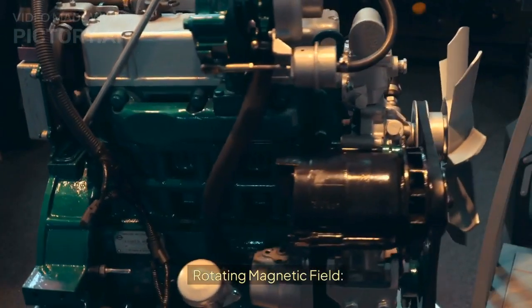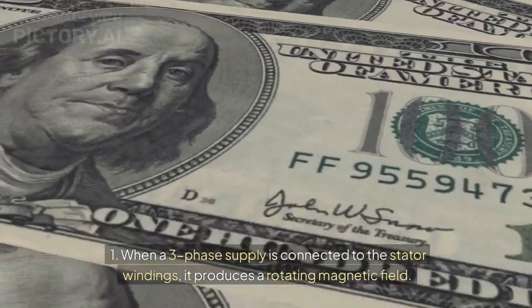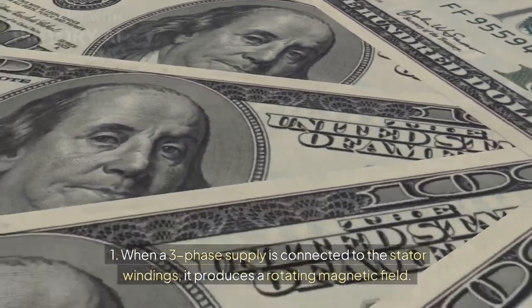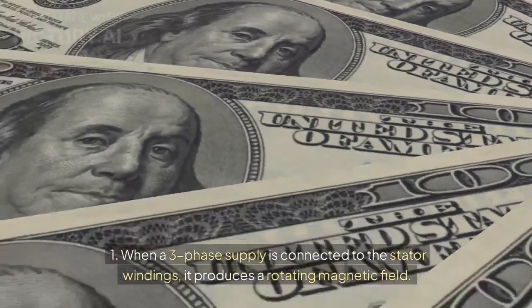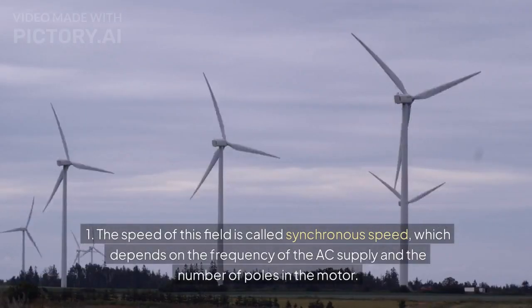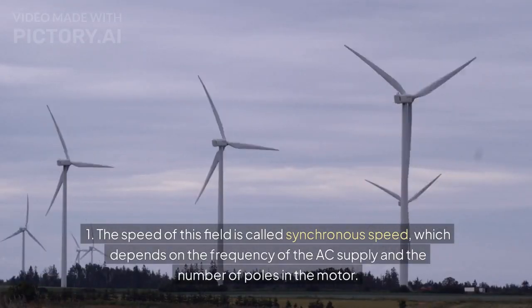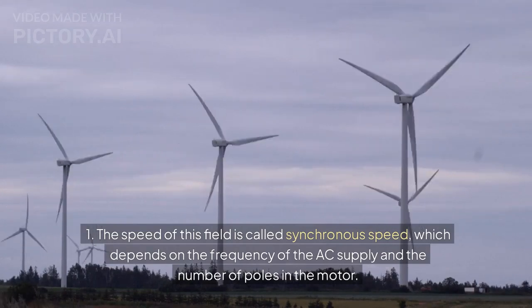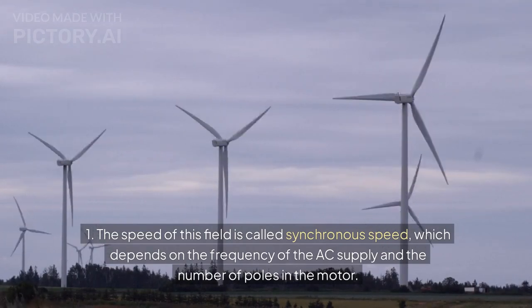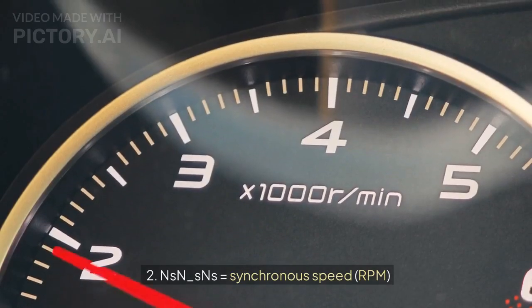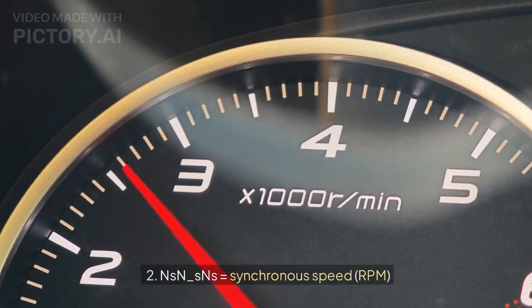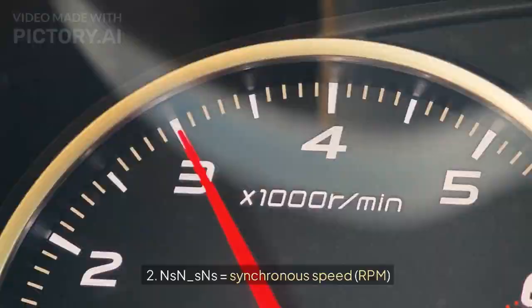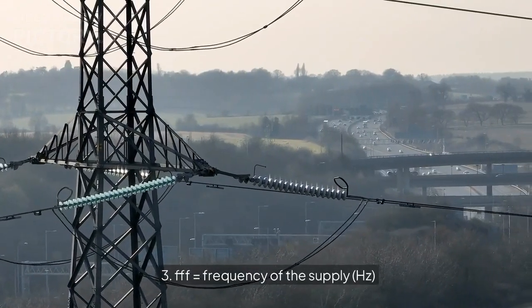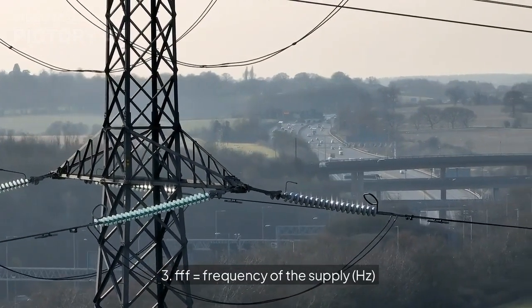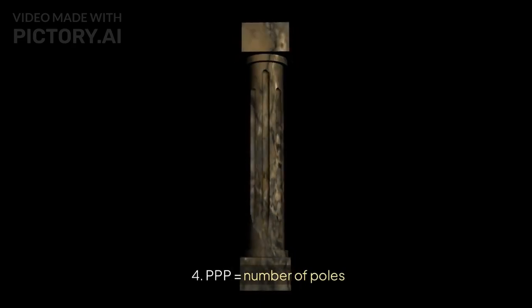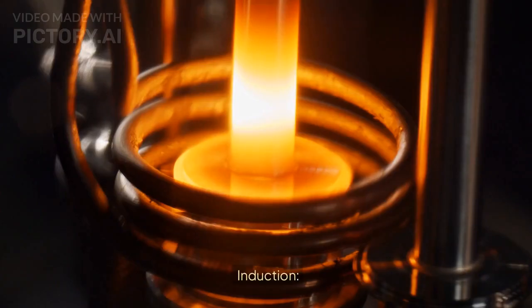Rotating magnetic field. When a three-phase supply is connected to the stator windings, it produces a rotating magnetic field. The speed of this field is called synchronous speed, which depends on the frequency of the AC supply and the number of poles in the motor. N_S equals synchronous speed, RPM. F equals frequency of the supply, Hz. P equals number of poles.